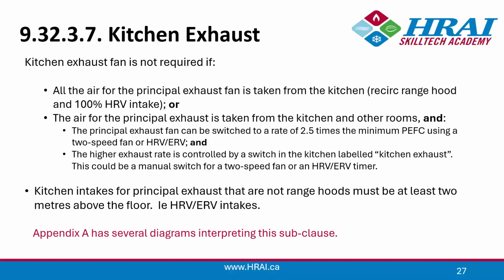In that case, you can make it what you want to make it. So there's a fair degree of flexibility here, as long as it does return to the lower setting. And of course, there are many new HRVs out on the market that are digitally balanced, so we can really hone in on these numbers and set a high and a low that are specific. Whereas in the non-digitally balanced units, of course, you're balancing on high and the low takes care of itself.